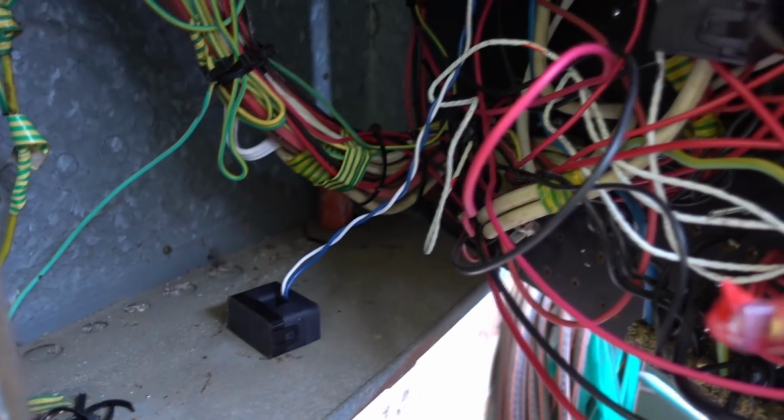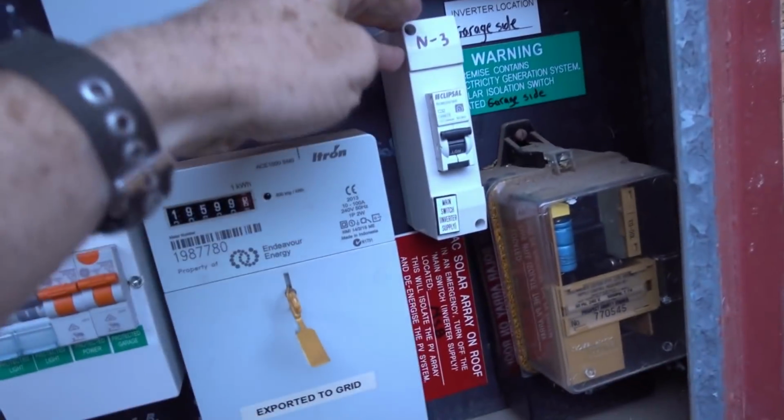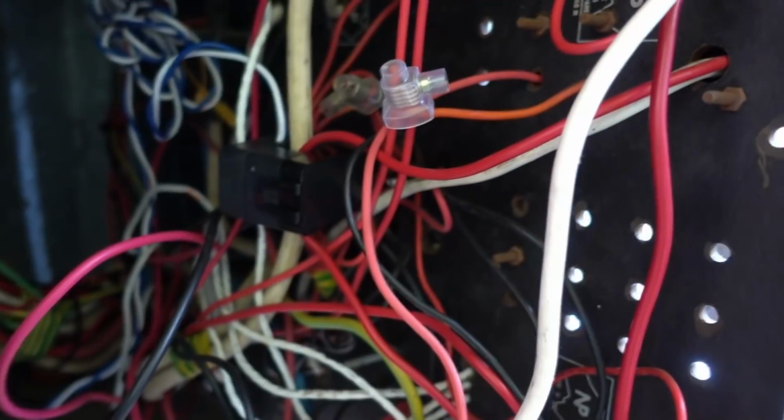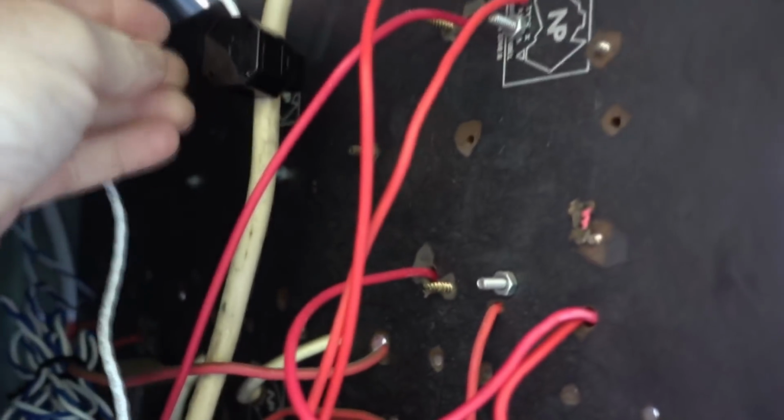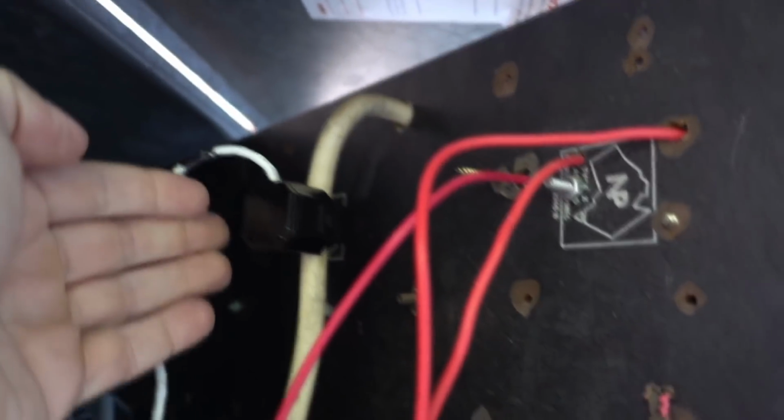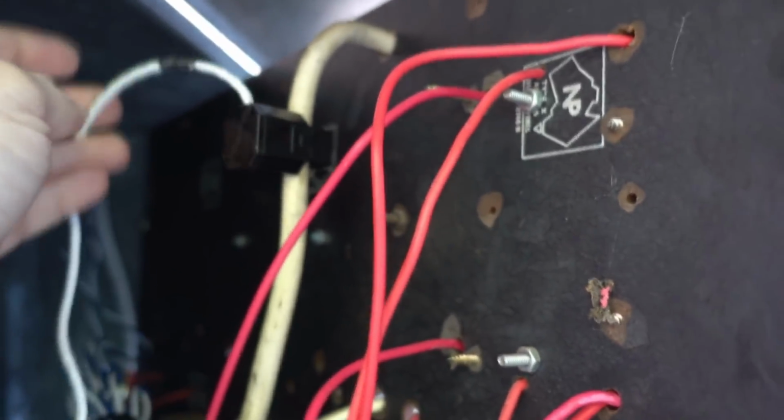So the other production transformer that's in parallel, it's not actually in the box here. It's not actually on there. It's actually up in there, which we didn't have to actually touch. So what we have to do now, so the change I had to make, if you remember, the consumption transformer, which is this one here, it was up the top here. It was just on that main 60 amp breaker coming into the property here. This is the one for the solar analytics system, so I haven't touched that at all. So this one used to be up here. Where you actually put it there actually makes no difference.